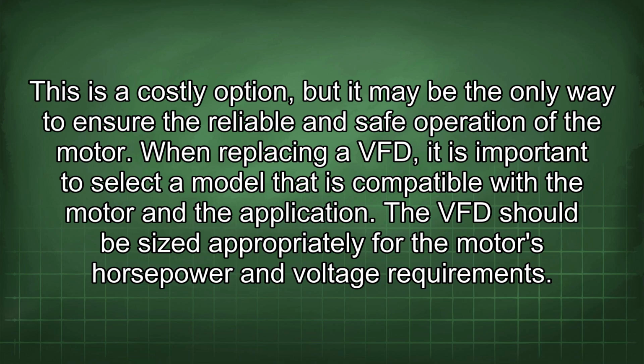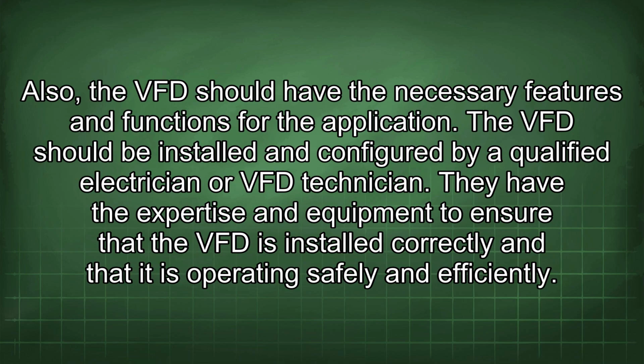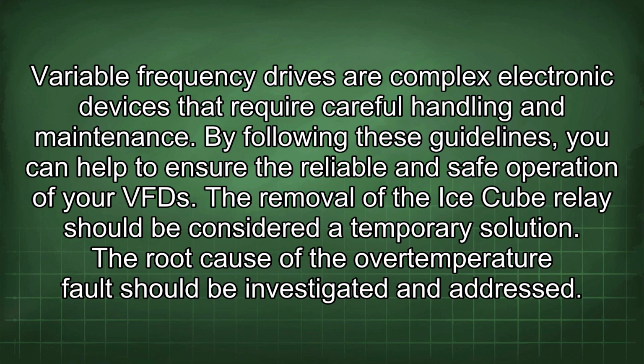This is a costly option, but it may be the only way to ensure the reliable and safe operation of the motor. When replacing a VFD, it is important to select a model that is compatible with the motor and the application. The VFD should be sized appropriately for the motor's horsepower and voltage requirements. Also, the VFD should have the necessary features and functions for the application. The VFD should be installed and configured by a qualified electrician or VFD technician. They have the expertise and equipment to ensure that the VFD is installed correctly and that it is operating safely and efficiently. Variable frequency drives are complex electronic devices that require careful handling and maintenance. By following these guidelines, you can help to ensure the reliable and safe operation of your VFD.